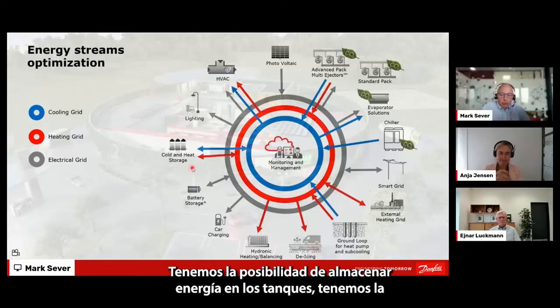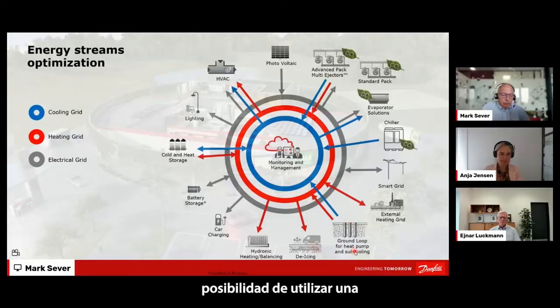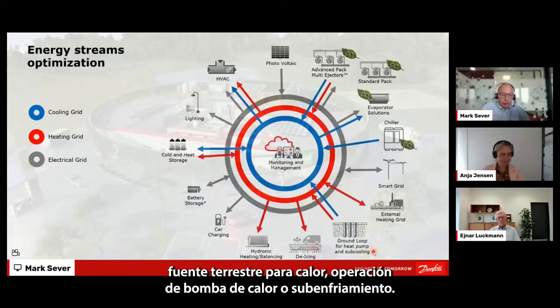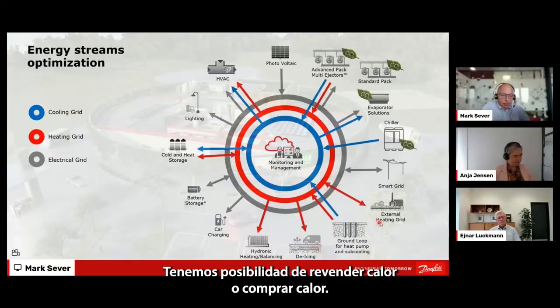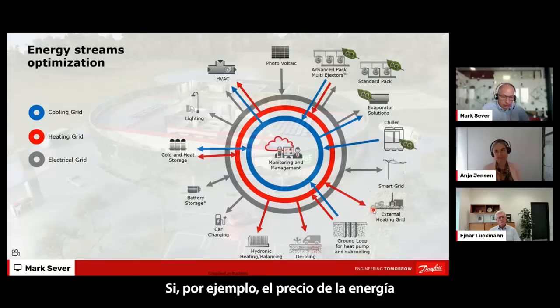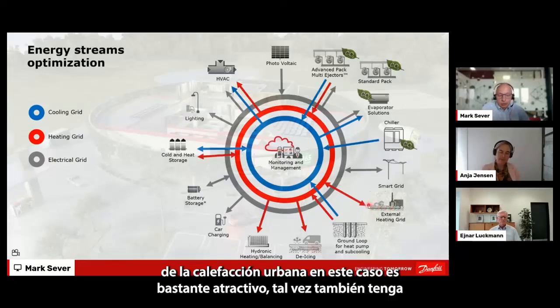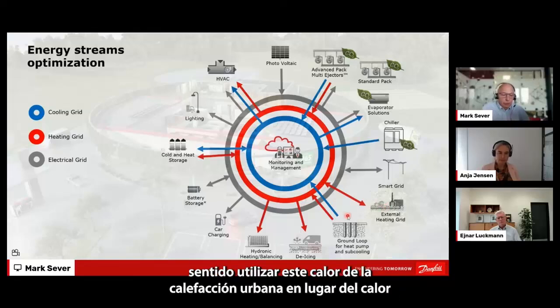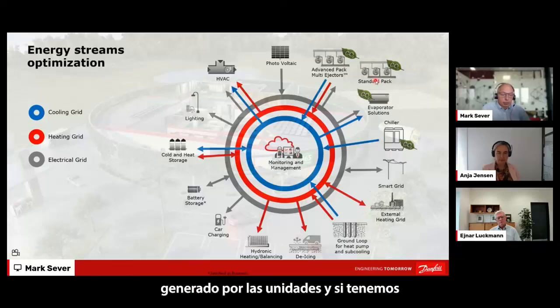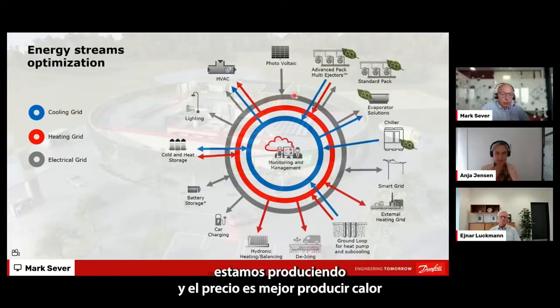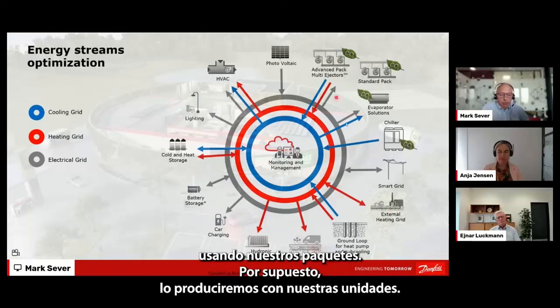We have the possibility to store energy in the tanks. We have the possibility to use a ground source for heat pump operation or subcooling. We have the possibility to resell heat or buy heat if, for example, the price of energy from the district heating is quite attractive. Maybe there is a sense to use this heat from the district heating rather than produce it ourselves. Vice versa, if we have a situation where we have additional electricity that we're producing and it's price-wise better to produce heat using our own system, of course we will produce it ourselves.